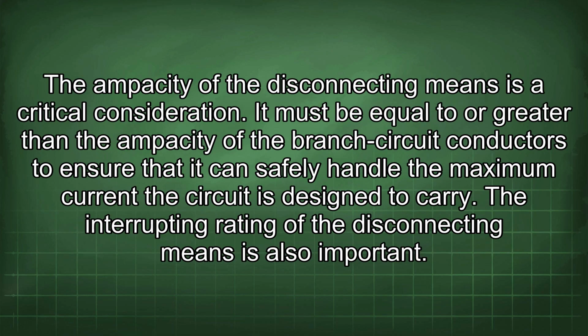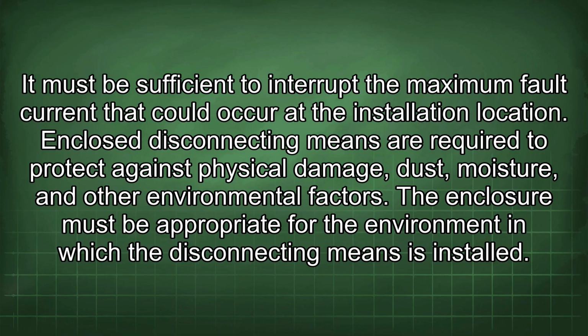The ampacity of the disconnecting means is a critical consideration. It must be equal to or greater than the ampacity of the branch circuit conductors to ensure that it can safely handle the maximum current the circuit is designed to carry. The interrupting rating of the disconnecting means is also important. It must be sufficient to interrupt the maximum fault current that could occur at the installation location.